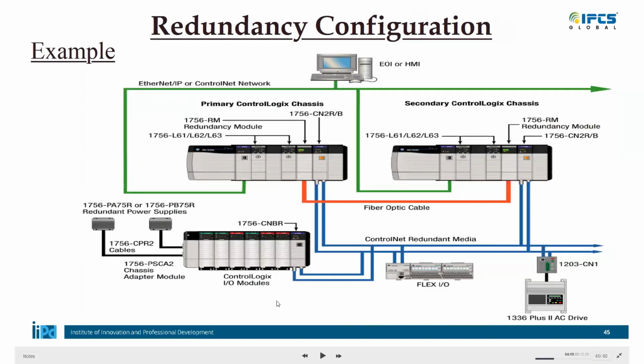One of the biggest advantages of having PLCs is the redundancy configuration. Redundancy means having a backup PLC which is running side by side. We have both hot and cold redundancy. Hot redundancy means both PLCs run simultaneously, and if one fails, the other automatically takes over. The second PLC, or the standby PLC, is waiting for the primary PLC to fail. Whenever the first PLC fails, the standby PLC automatically takes over control and keeps the system running. These systems are widely used in critical process systems, where you cannot shut down the machine immediately.